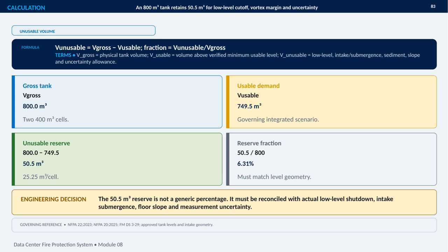The key engineering point is that this is not simply a generic percentage allowance. The reserve has to be reconciled with the actual low-level shutdown point, intake submergence requirements, floor slope, sediment, and measurement uncertainty. In other words, the calculated volume must agree with the tank's physical level geometry and approved operating levels. The governing references shown here include NFPA 22 from 2023, NFPA 20 from 2025, FM Data Sheet 3-29, and the approved tank and intake arrangement.